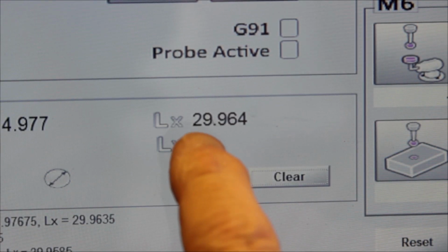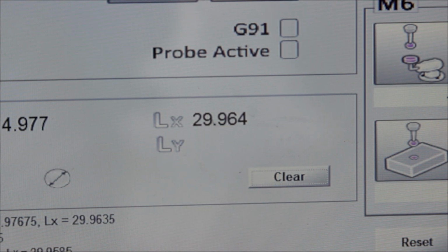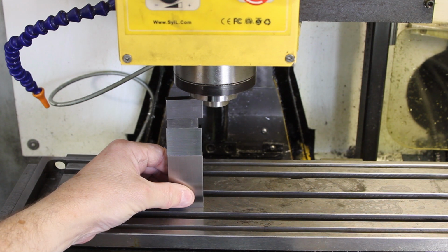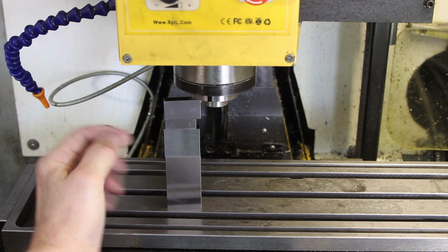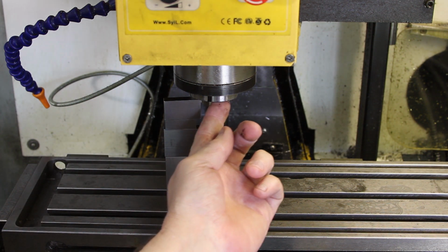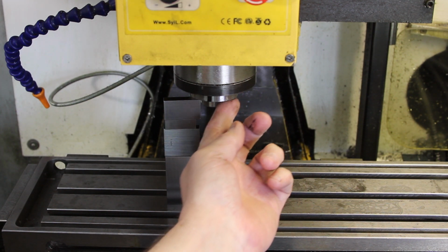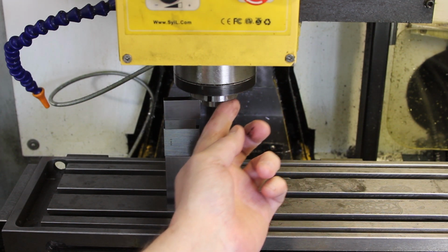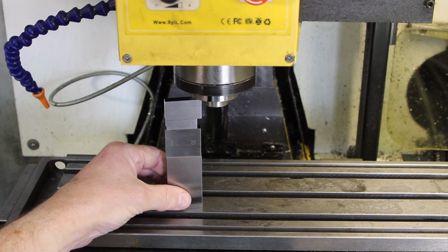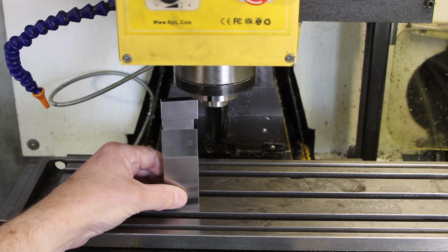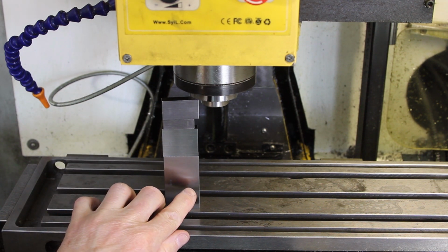There we go, it's come up with 29.96. That seems to be reasonably consistent, 29.97, 29.98. What I've got here is a bunch of gauge blocks under what I'm going to use as the reference surface, which is the bottom edge of the spindle. This is ground flat.